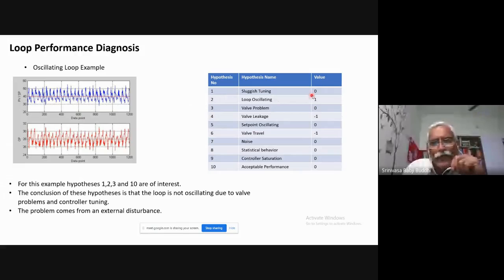Sluggish tuning is 0, that means it is false. Loop is oscillating is true. Valve problem is false. Valve leakage not sure. Set point is oscillating false. Valve travel is not sure. Noise is false. Like this. So finally we say that the loop is oscillating.